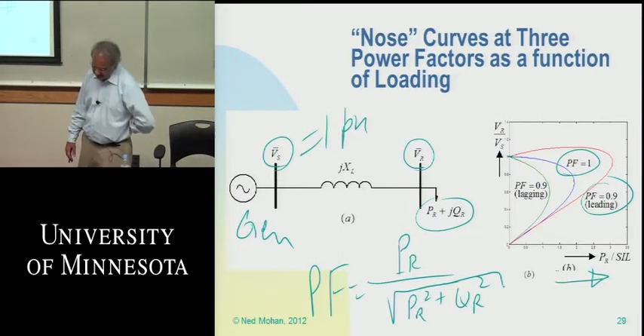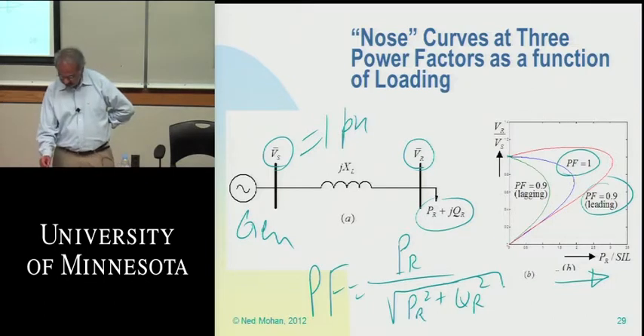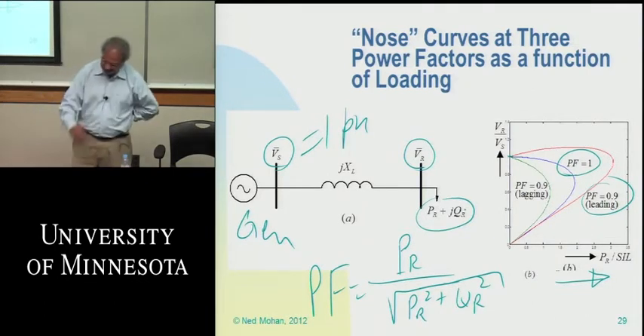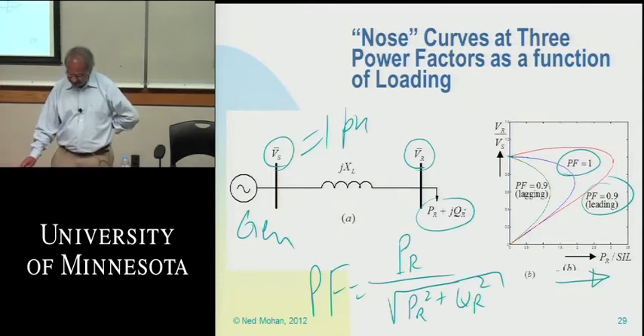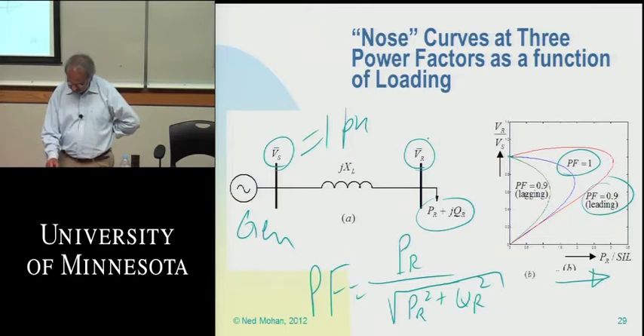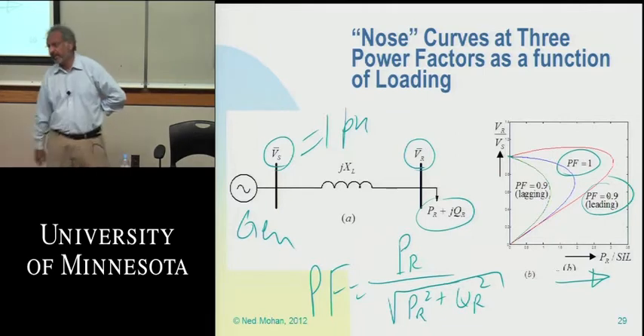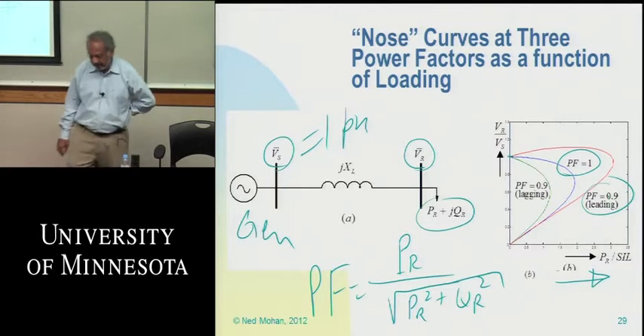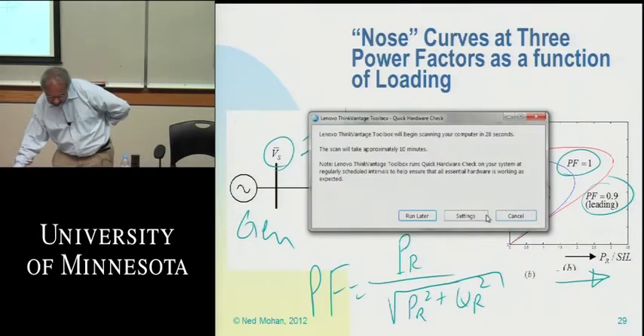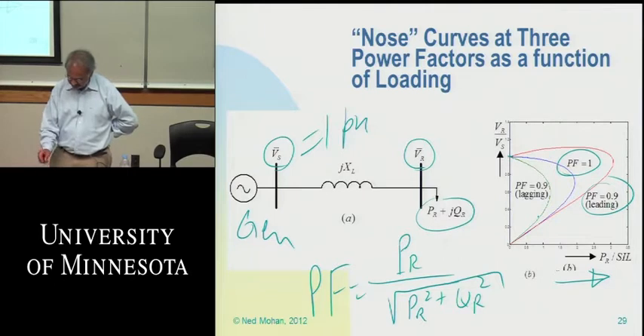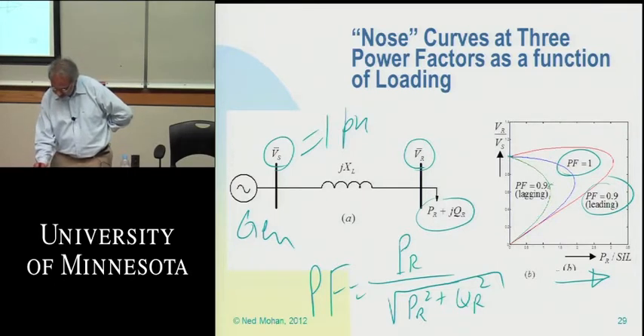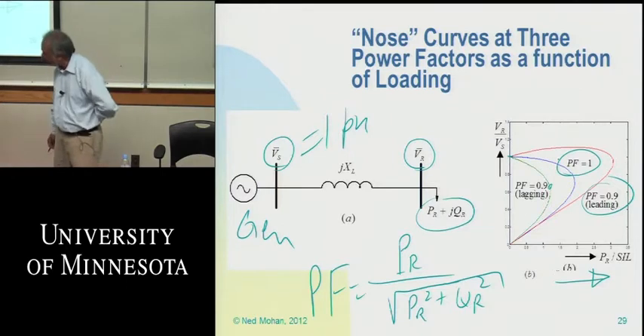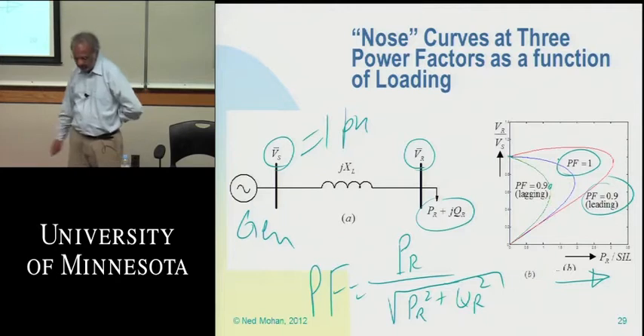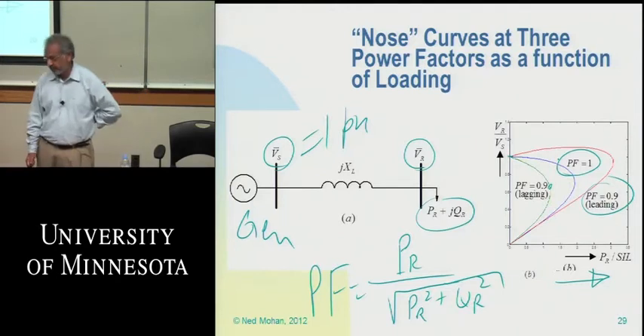This depends on whether the current in the load is leading or lagging the voltage. The amplitude of the receiving end voltage depends on power factor, as shown in these three curves. Beyond a certain point, the curve reaches instability - this is called a nose curve, because of its shape, and beyond that point the voltage collapses to zero, which is an unstable point.